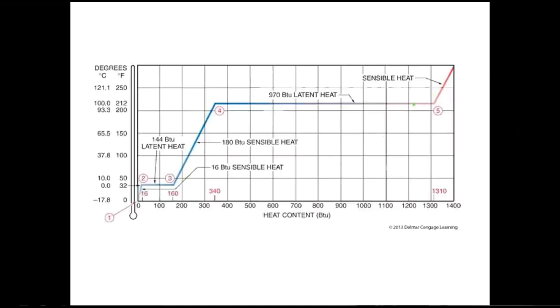So if you take your saturation temperature and then you measure the temperature of the liquid, the difference is subcooling. Now, on our chart, that's what happens right down here. So here we're at saturation point. We're dumping all of the latent heat. At this point, from here downwards is our subcooling. So we'll get into this again in more detail, but actually the entire refrigeration cycle happens between subcooled liquid through the saturation point up to superheated vapor, and then back down again down to this chart. When we get into the refrigeration cycle, we will explore this chart a little bit further.